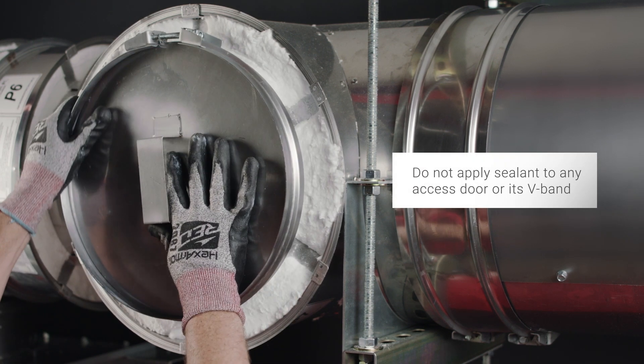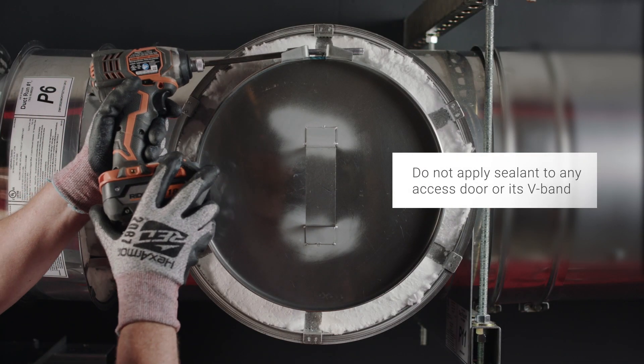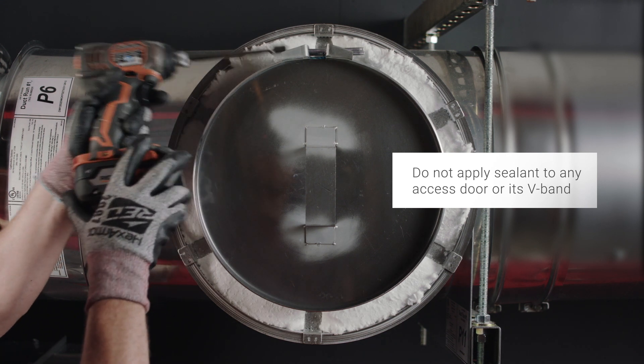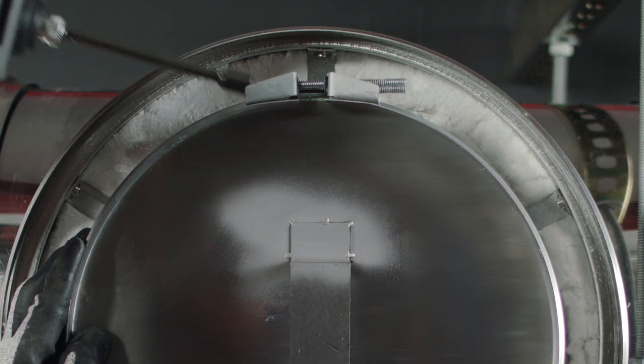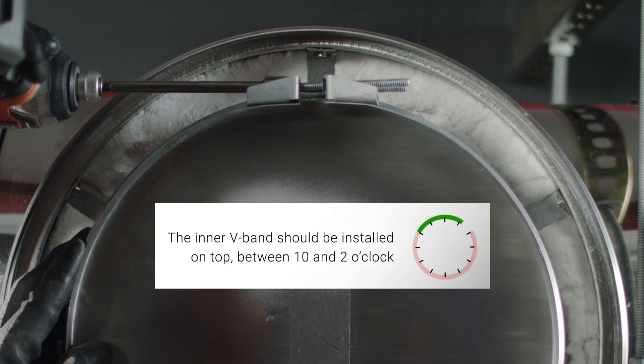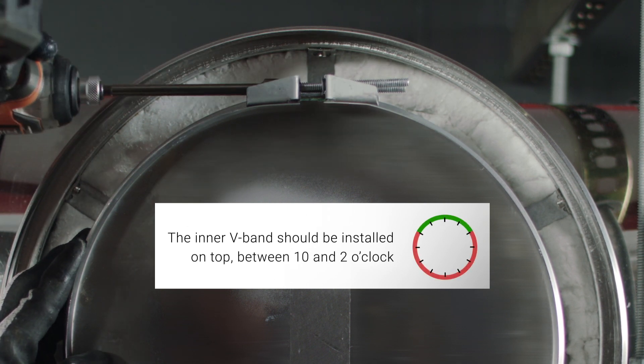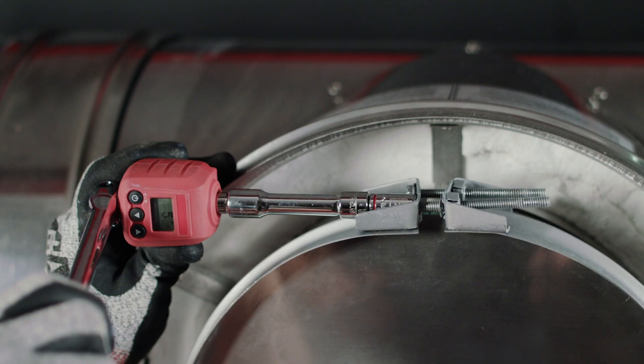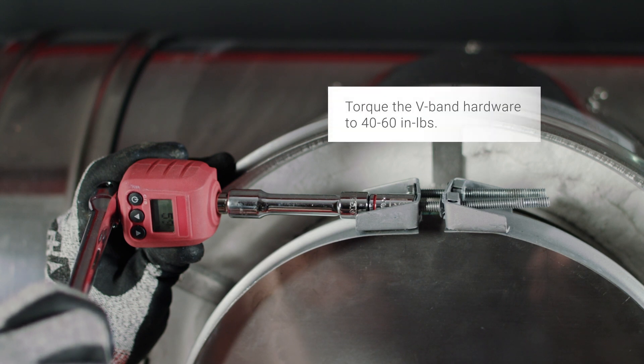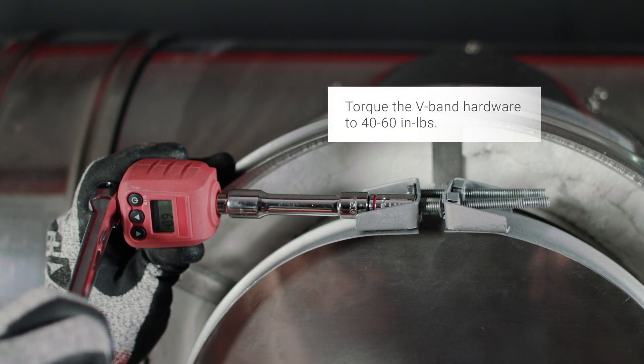To facilitate future access, do not apply sealant to the V-band on any access door. The V-band hardware should be located on the top side of the access door between 10 and 2 o'clock. Tighten the V-band hardware to a final torque between 40 and 60 inch-pounds.